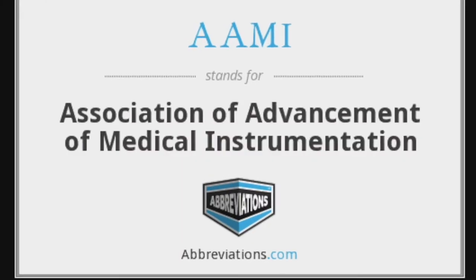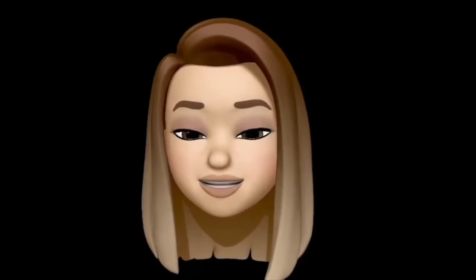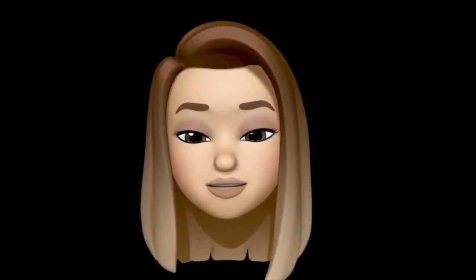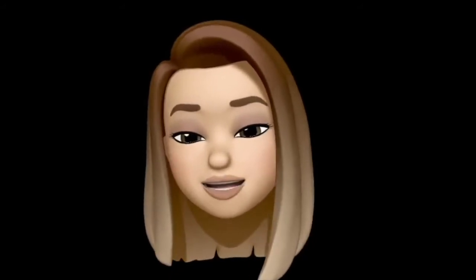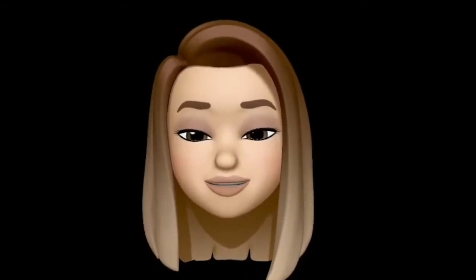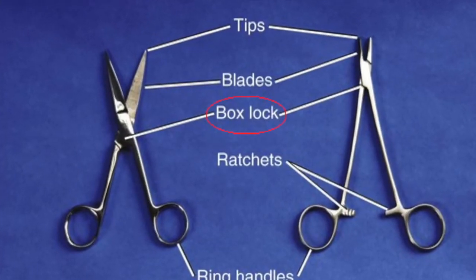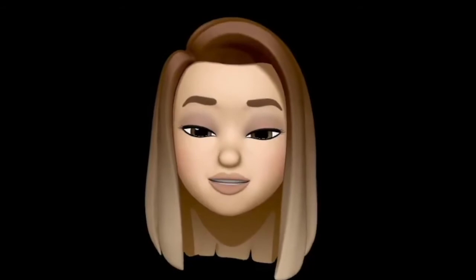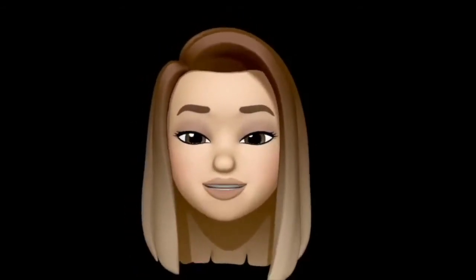Surgical instrument etching was one of the first practices used. This practice involves carving the instrument's information into the instrument directly. This may have been easy and convenient to do and relatively inexpensive, but the risk it posed to patient safety was tremendous. According to the Association for the Advancement of Medical Instrumentation, this process can damage the hard, protective chromium oxide layer known as the passivation layer and create an area where bacteria can grow and where rust and corrosion could occur as well. Carving the instruments can also weaken the box lock and create fissures where microorganisms can hide and easily be missed during the cleaning process. This practice is no longer in use due to the risk of infection it poses to patients.